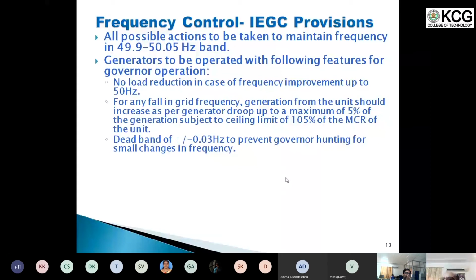So the governors are set such that up to 50 hertz frequency, there is no load reduction. For any fall in grid frequency, the generating unit shall increase its generation as per the droop, up to a maximum of 5%. And a dead band in the governor will be provided up to plus minus 0.03 hertz, so as to avoid any hunting of governors for a small change in frequency. The grid code provides that generators will have a droop setting of 3 to 6%. This is required for the parallel operation of the generators. And droop essentially means the percentage change in speed or frequency when you go from no load to full load.